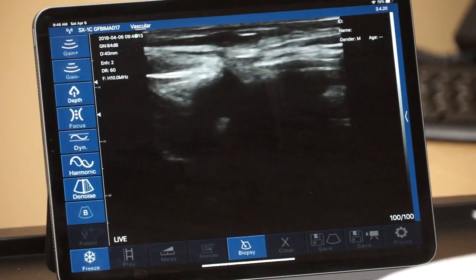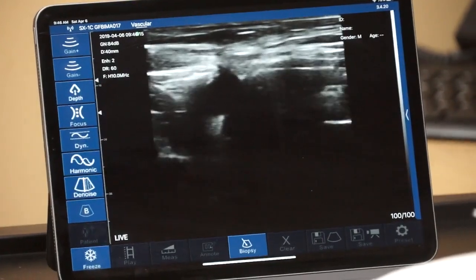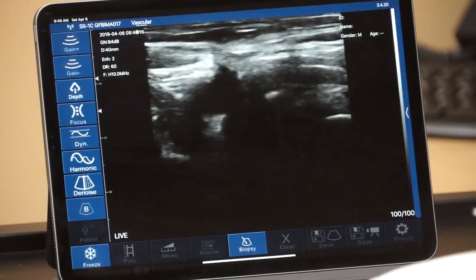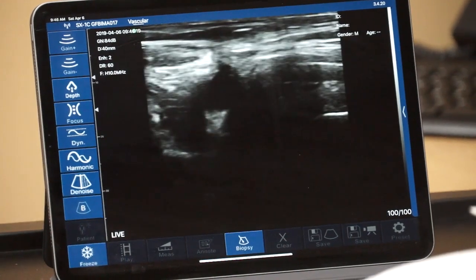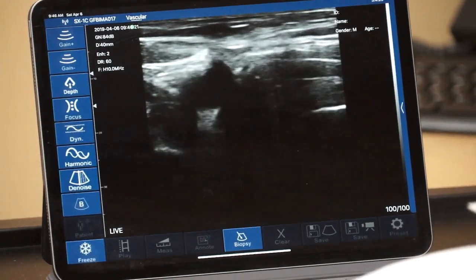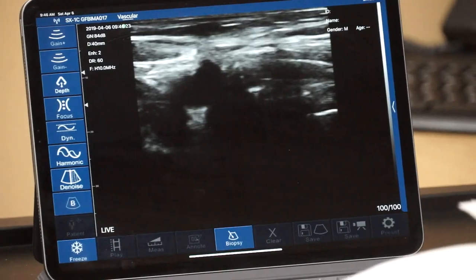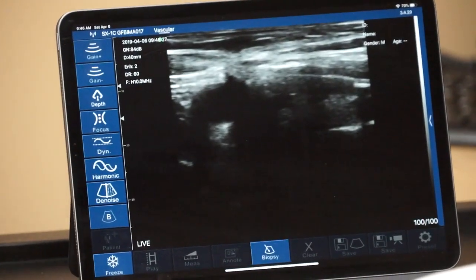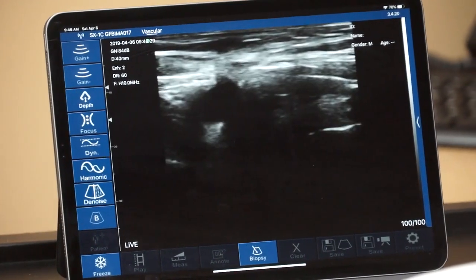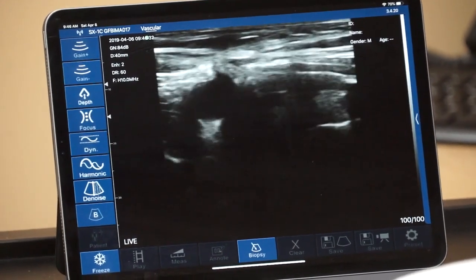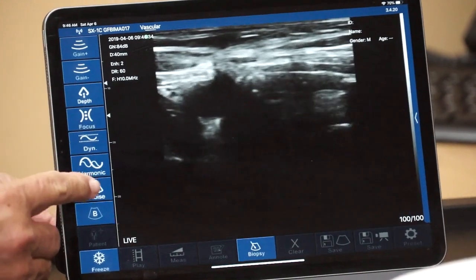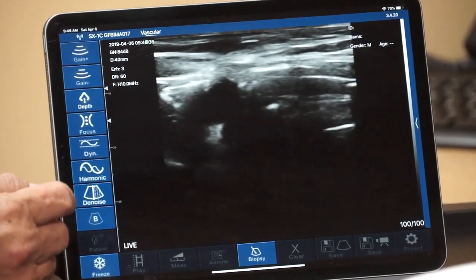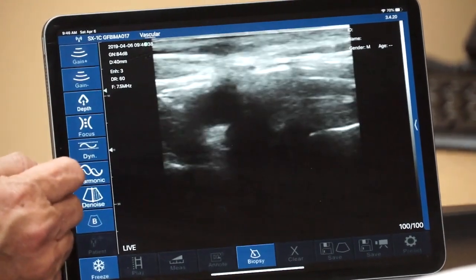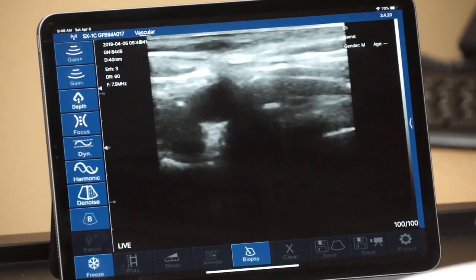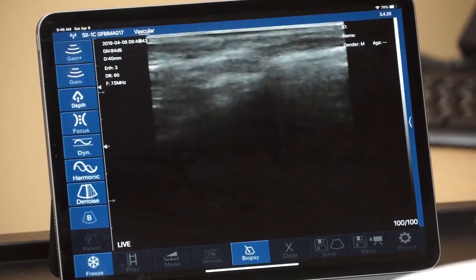The next button down is labeled harmonic, but this is where we control the frequency. On this device, the two frequencies that the linear probe scans are 7.5 and 10 megahertz. That's labeled next to the letter F in the area of the parameters. Right now we're scanning at 10 megahertz. Once Dr. Garcia hits the harmonic button, it will change to 7.5, and the image quality changes a little bit.